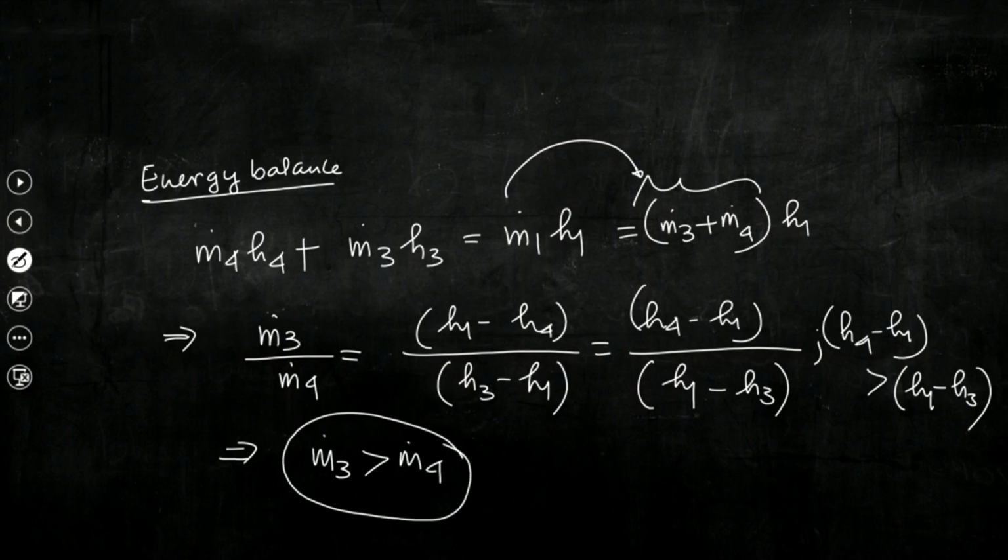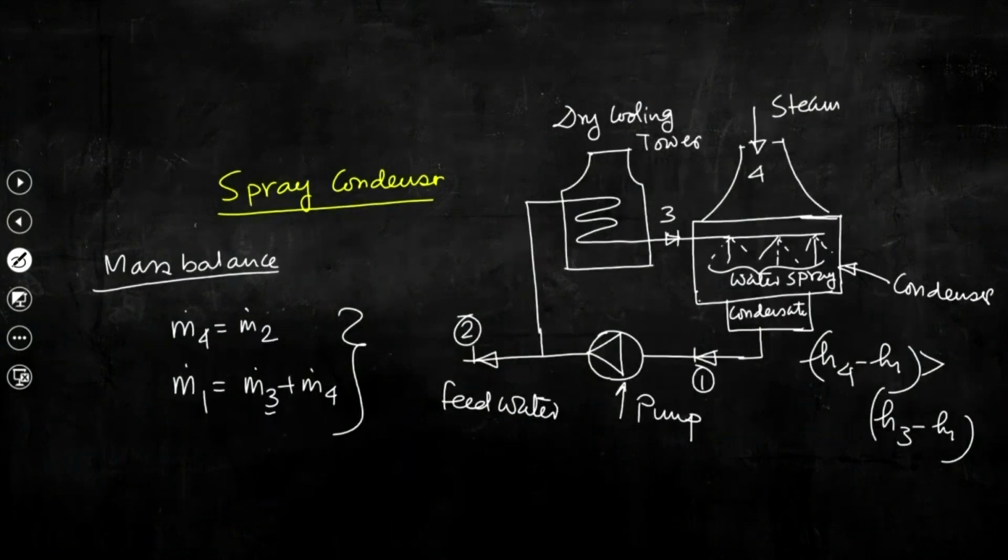So, that is what I was discussing few minutes back, that this particular unit will be designed in such a way that the amount of coolant flow will dictate that the condensate which would be available at the inlet of the pump should be saturated liquid.